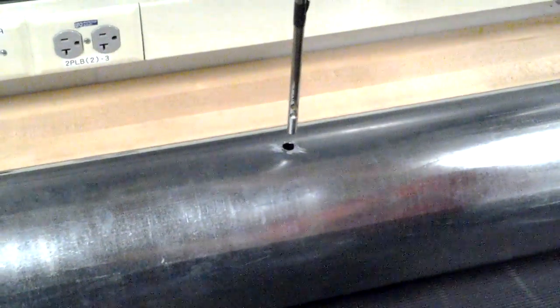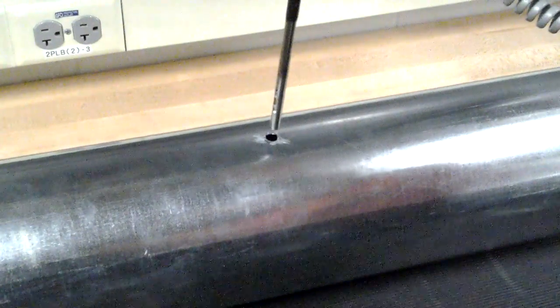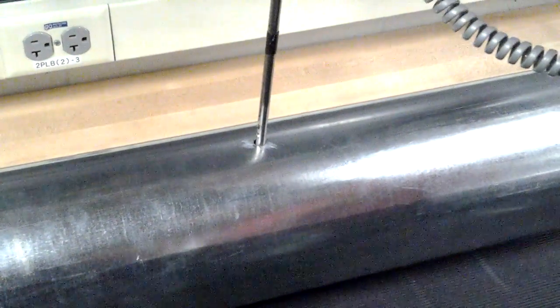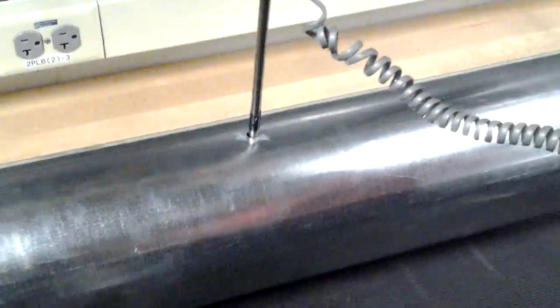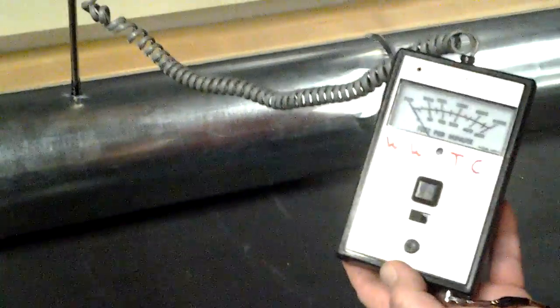The flow holes through the probe tip must be parallel to airflow. It will be helpful to observe the orientation of the insertion depth scale along the side of the probe tip to keep the tip properly aligned.